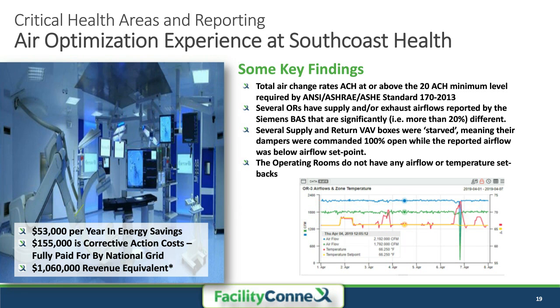Here's some great examples of issues detected above and beyond what your BMS, or even an individual, can jump on and look at. Can an individual come in and actually figure out his air change rates from the BMS? Typically not. Typically you bring in a certified air balancing company into your environment, and you do this once a year, maybe once every couple of years. By that time, you've already wasted months of energy. So you want to do that kind of balancing and focus.